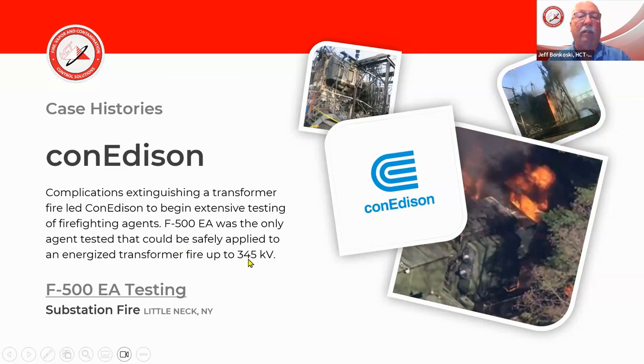And they've done testing up to 345 kilovolts. And we've got instances where the F500 has been used to extinguish these transformers, requiring less water, having less of an impact on the environment. Where when other products have been used, we're looking at possibly millions and millions of dollars in cleanup costs. Where with F500 being used, it's basically been able to stay within the diked area where these transformers are.